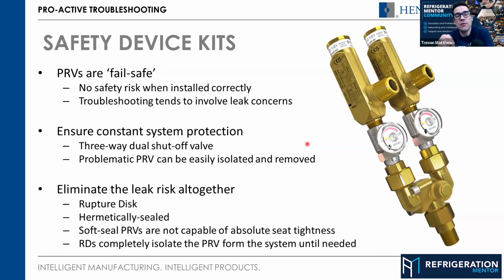So now, valve manufacturers, if one here in Canada goes off, and then it seats, depending on how fast it goes off, how quick the pressure goes up, and that reseats, and then you're out in New Zealand and it goes off. The same valve, same manufacturer, off the same line, one beside the other, doesn't mean it'll be the same percentage afterwards. And that's why every manufacturer I've talked to recommends that if the relief goes, it should be replaced or repaired.